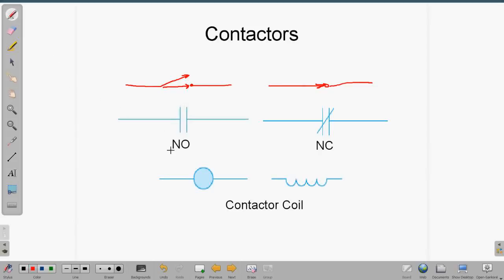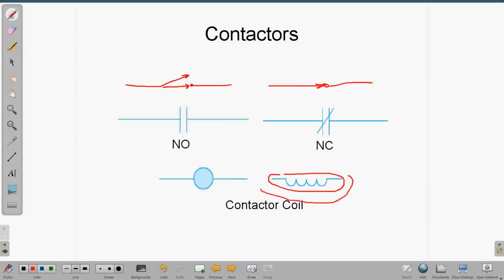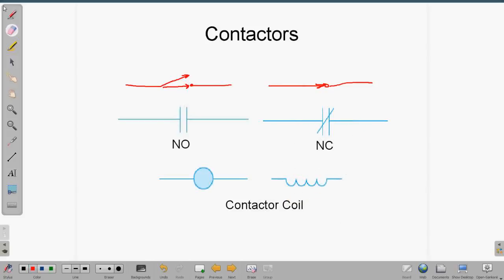Let's go over that again. A normally open contact is not made and doesn't allow power to pass through when there's no power applied to the coils. A contactor and relay can also have a normally closed contact, which means when there's no power applied to the coil, that contact is still closed and does allow current and voltage to pass. Normally open: no power applied, contact is open. Normally closed: no power applied, switch is made, voltage and current can pass.